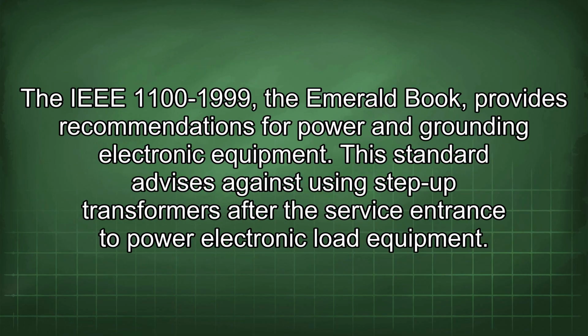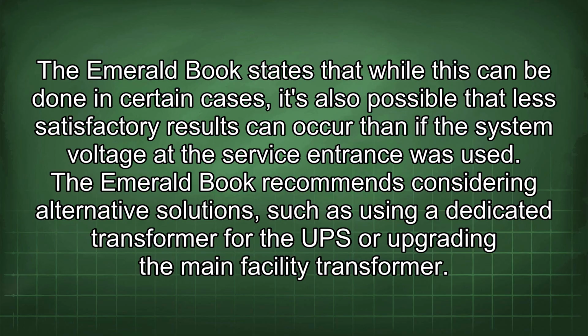The IEEE 1100-1999, the Emerald Book, provides recommendations for power and grounding electronic equipment. This standard advises against using step-up transformers after the service entrance to power electronic load equipment. The Emerald Book states that while this can be done in certain cases, it's also possible that less satisfactory results can occur than if the system voltage at the service entrance was used.